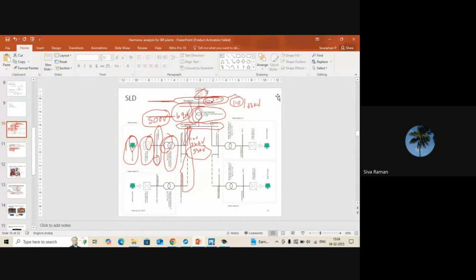This power quality analyzer is generally made for voltage up to 1 kV. Whenever the voltage is more than 1 kV, we have to connect the power quality analyzer to the available CT and PT at the site. The CT and PT have a reduced voltage and current. Mostly the CT will be 1000 ampere by 1 or 1000 ampere by 5, so the secondary current will be 1 ampere or 5 ampere. We have to connect it at the 5 ampere or 1 ampere side.